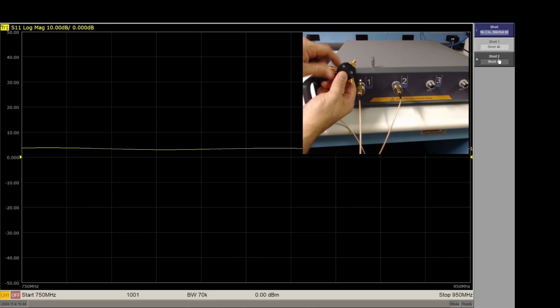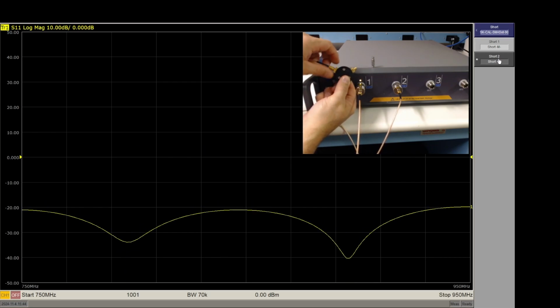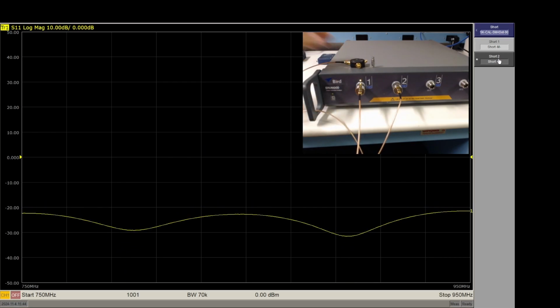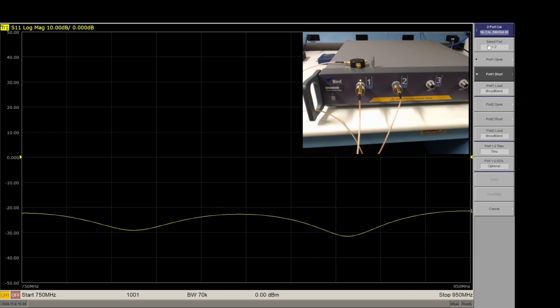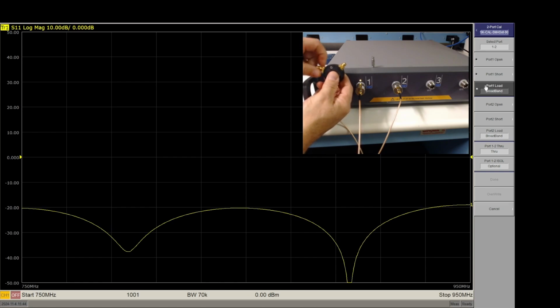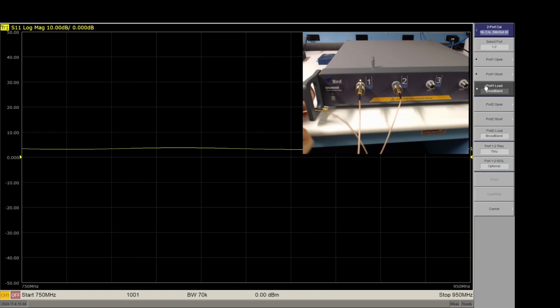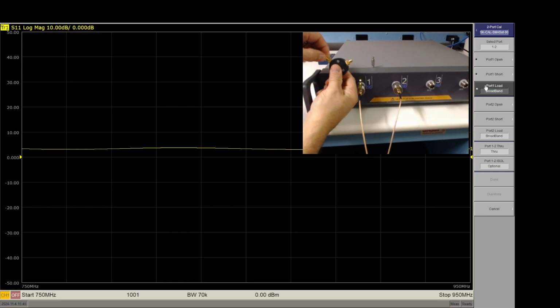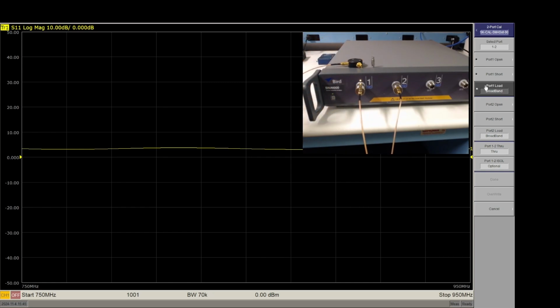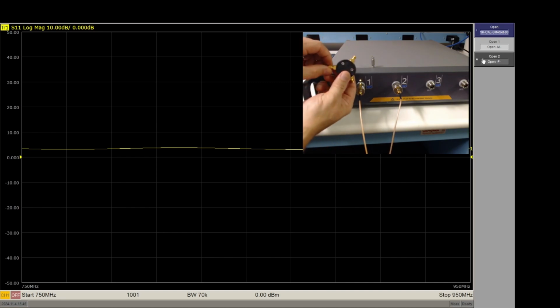Connect the part of the standard marked with an L for load to the end of the cable. Again, use the function buttons to navigate up a level and click on the port 1 load button. Connect the part of the standard marked with an O for open to the end of the cable leading from port 2. Click on the port 2 open button in the software interface, then click the Open F since the connector type on the standard is female.